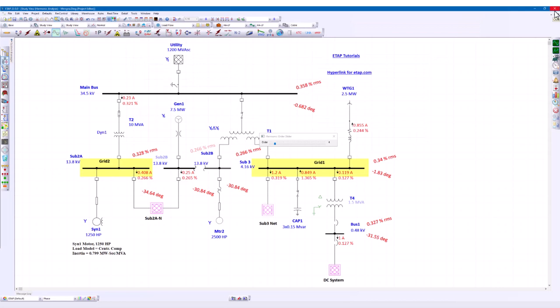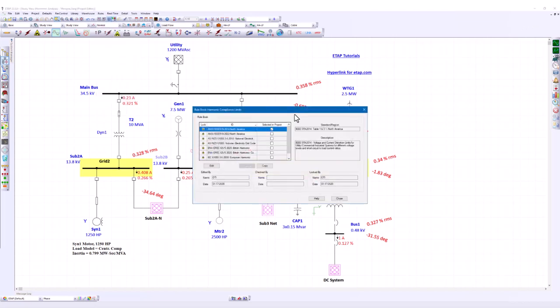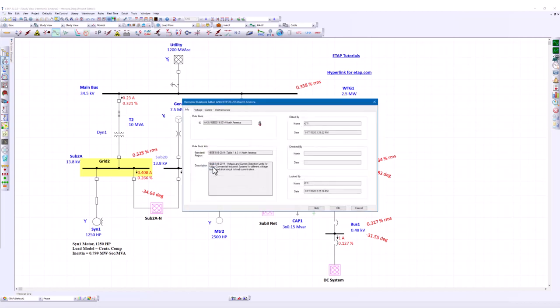When we perform harmonic load flow studies, one important goal is to evaluate the total harmonic distortion and individual harmonic distortion against the standards. Also, we need to evaluate the capability of all the devices like cables, transformers, capacitors, filters, etc. So let's start seeing where we can define the limits of all the harmonic voltage and current distortions. Let's go to Rules, Harmonics. Under the harmonic rulebook, you will see a list of harmonic rules based on different standards and grid codes that have been predefined by ETAP. Let's click on Edit and take a look at the format.